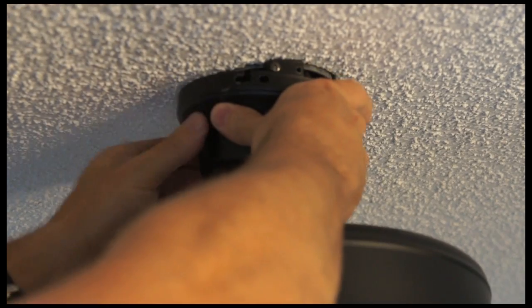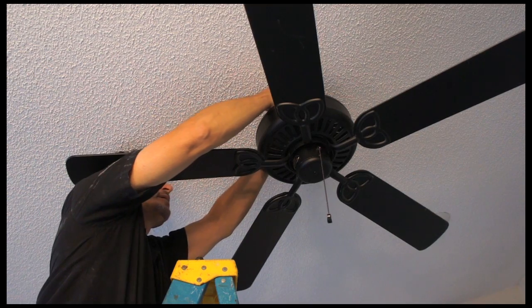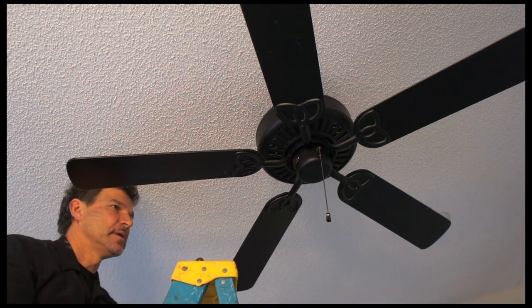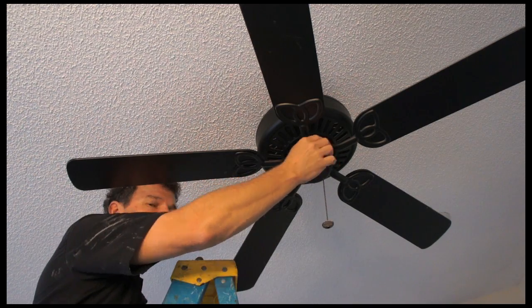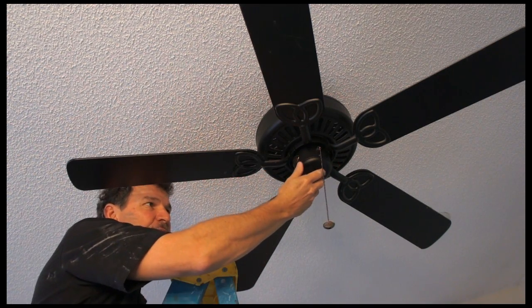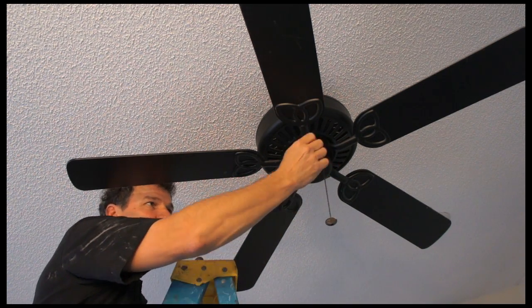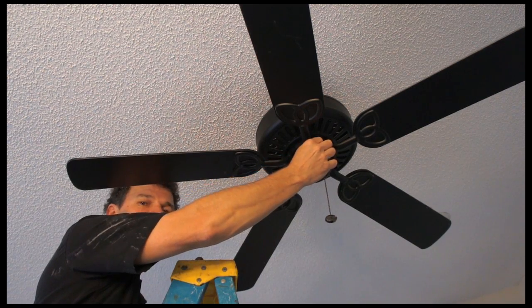So the only other problem, I'm going to put the canopy back on. The only other problem could be within the pull switch itself. In that case, you'll have to remove the bottom cover and replace the pull switch.